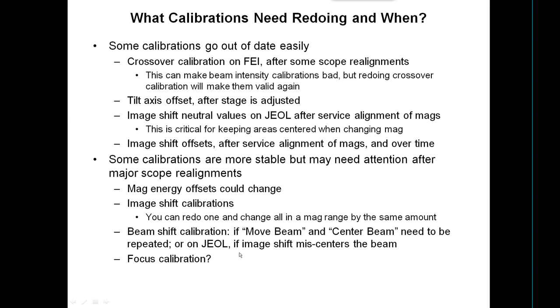On JEOL, there are so-called neutral values for the image shift. If those get redone on the microscope, SerialEM needs to know the new values too — this is critical for keeping the area centered when changing mags. You need to know when this has happened and run the calibrate image shift neutral value routine to record the new values into the calibration file. Image shift offsets also go bad after service alignments and seem to change a little over time, so they need more constant attention.